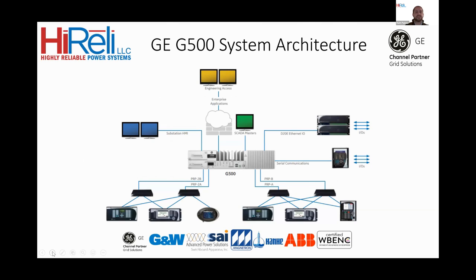Furthering the automation side, I've put a picture here of the G500 system architecture and how it integrates with your system. So the G500, it's a robust security environment providing seamless integration with your existing solutions. So whether it's an existing substation or you have a new one going in, the G500 is the RTU that you want to use. It collects data from substation protection, control, monitoring, RTU, and other IEDs, such as what you can see here. It processes all the data and then moves it up to your EMS or DMS SCADA systems, providing a centralized management system.